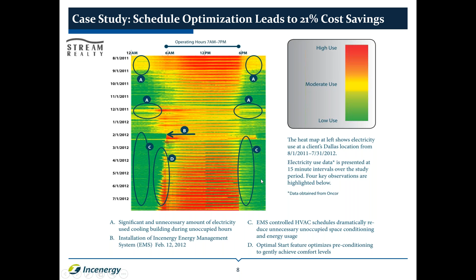Next case I want to show you is with another client of ours, where they have a number of locations, and we have used energy metering across all of those locations so that we're able to break down the usage into areas of the buildings. And by doing this, we're able to quickly identify where the energy spikes, where the energy peaks are occurring. And so we can take a series of buildings or a series of meters together, and these are sub-meters, and we'll just highlight those meters and be able to see what the consumption is.